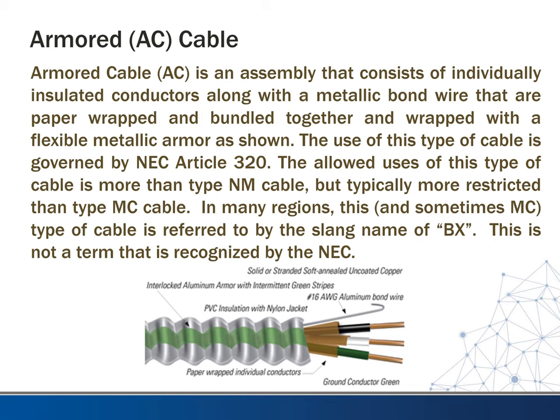Next, we want to look at armored cable, which is many times referred to as AC cable. This is an assembly that consists of individually insulated conductors along with a metallic bond wire that are paper-wrapped and bundled together and wrapped with a flexible metallic armor, as shown in the picture. The use of this type of cable is governed by Article 320 of the National Electrical Code. The allowed uses are probably more than NM cable but typically more restricted than type MC cable. In many regions, this and sometimes MC cable may be referred to by electricians as BX, though this abbreviation is not recognized by the National Electrical Code.